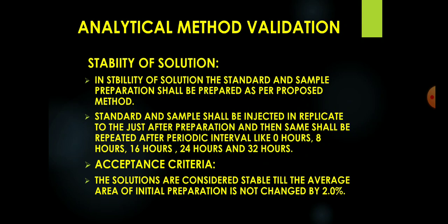The standard and sample shall be injected in replicate just after preparation, and then the same shall be repeated after periodic intervals like 0 hours, 8 hours, 16 hours, 24 hours, 32 hours, or any other periodic intervals can be chosen. Acceptance criteria: the solutions are considered stable till the average area of the initial preparation is not changed by 2%.